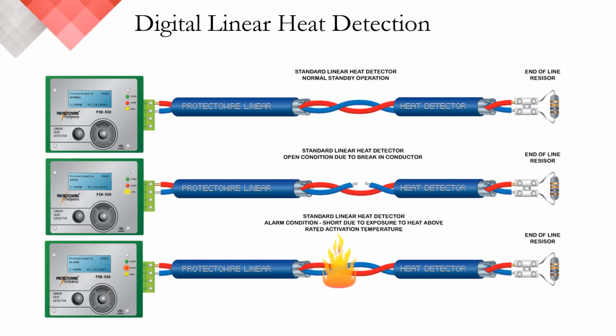And finally, as depicted in that third image at the bottom of your screen, when there is a heat event or a fire that meets or exceeds that 135 degree Fahrenheit or 57 degrees Celsius, the heat-sensitive polymers weaken or melt, allowing those metal spring steel conductors to make contact, forming an electrical short. This short then bypasses the end-of-line resistor, causing a change in resistance to the circuit that allows the supervisory equipment to initiate an alarm condition.